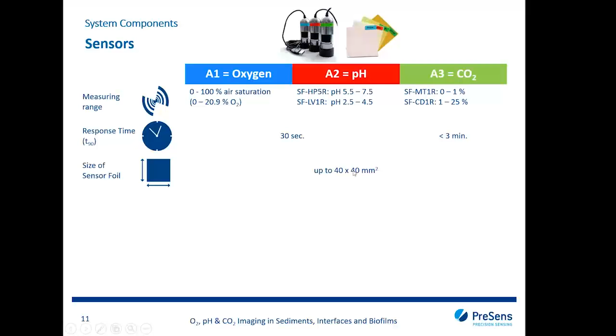The response time of oxygen and pH sensor foils is below 30 seconds, and in case of CO2, it's below 3 minutes. The sensor foil can have different sizes with a maximum of up to 40 times 40 square millimeters, which is also the maximum field of view of the detector. But it has a focus-adjusted field of view, so you can also choose a smaller field of view. The number of sensing points you generate within one recorded image is more than 300,000. They are recorded at the same time in one image. And they work in a temperature range from 5 degrees up to 45 degrees centigrade.